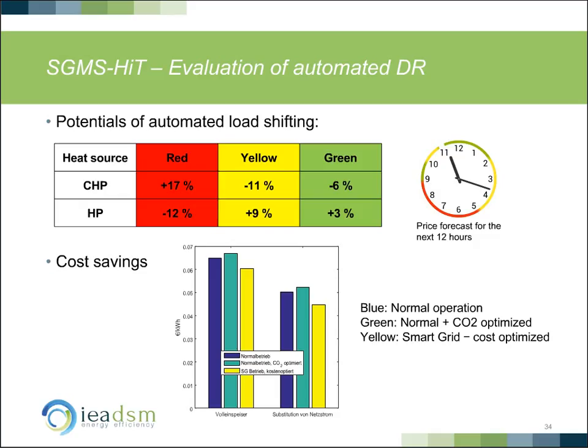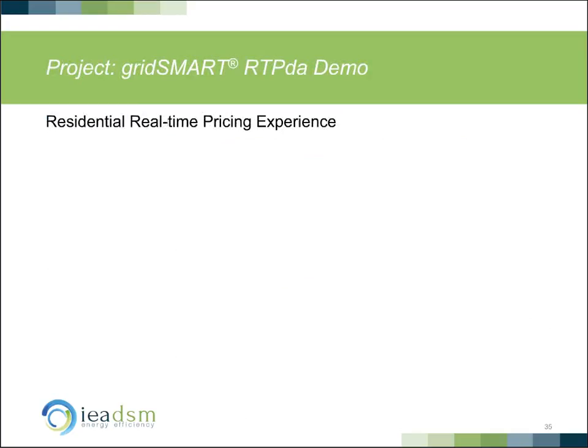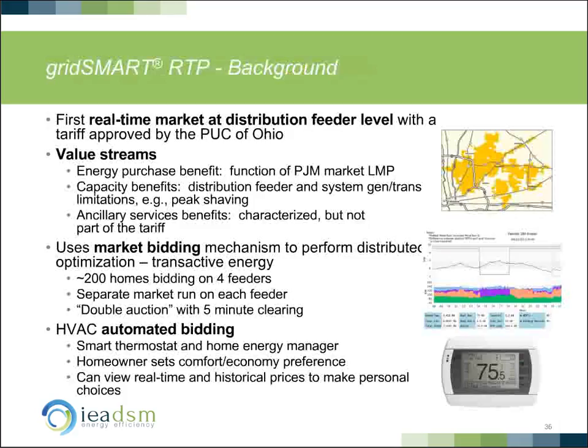When we look at the results from the automated demand response part, you see that the intelligent usage of the energy sources for the warm water can be optimized, using the CHP in times where the network congestion is high, or where they can get more money out of that red area. And the CHP is reduced where the electricity price or the network tariff in that case is cheap. Also, they can increase the usage of the heat pump in times where there is a low price.